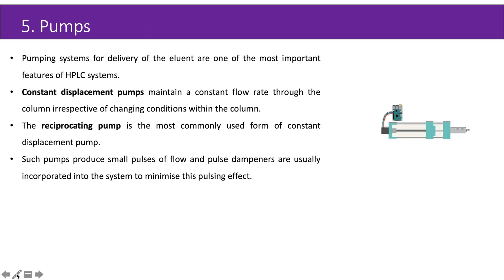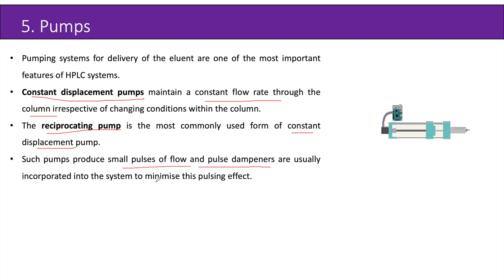Next are the pumps. The pumping system for delivery of the eluent is one of the most important features of HPLC systems. A constant displacement pump maintains a constant flow rate through the column irrespective of changing conditions within the column. The reciprocating pump is the most commonly used form of constant displacement pump; such pumps produce small pulses of flow, and pulse dampeners are usually incorporated into the system to minimize the pulsing effect.